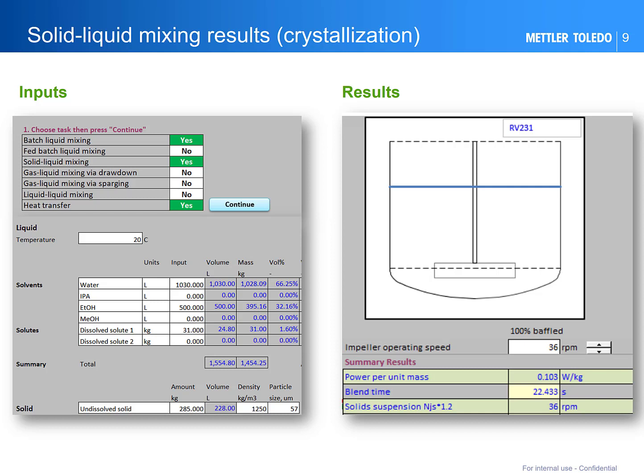Multi-phase mixing calculations are done much in the same way as for single phase, but you choose a different task. In this case we've chosen solid-liquid. In addition to putting in the vessel amounts and the amounts of solvents, you also put in the amount of solid, and on the right-hand side it shows the results — calculating the power per unit mass, blend time, but also now the solid suspension NJS. We use a safety factor of 1.2, as the correlation is accurate to plus or minus 20%, so this tells you we need to run at 36 rpm to suspend these particular solids.